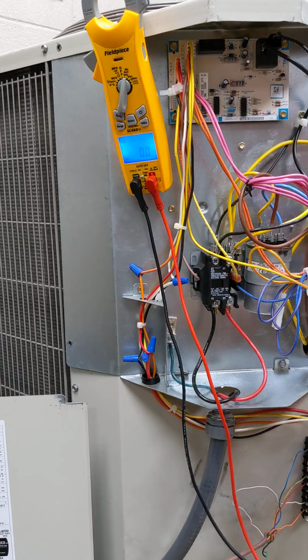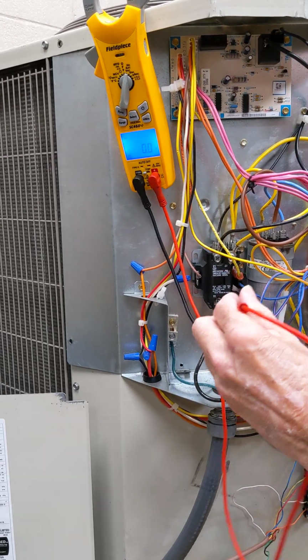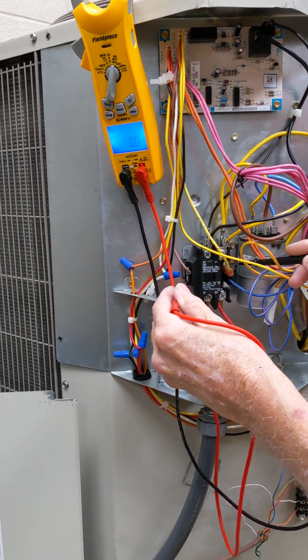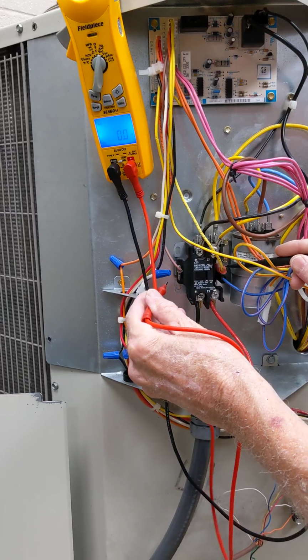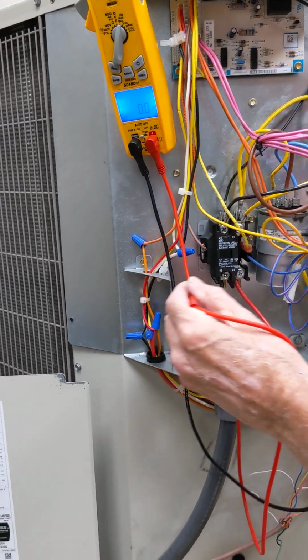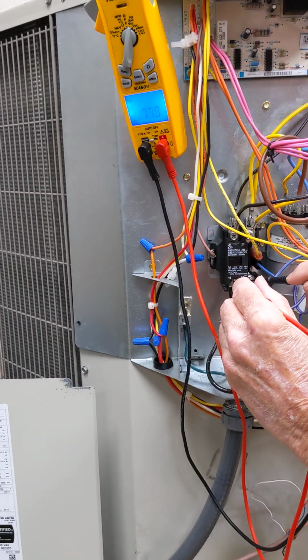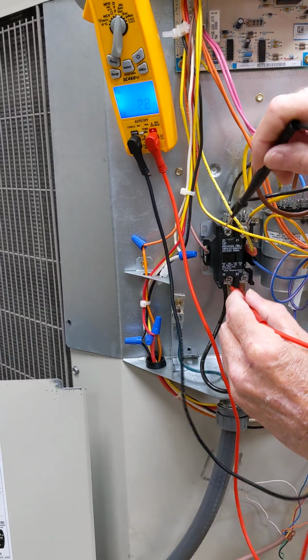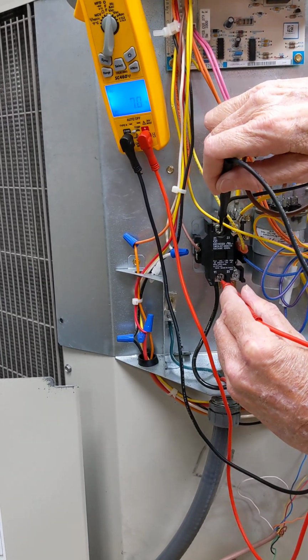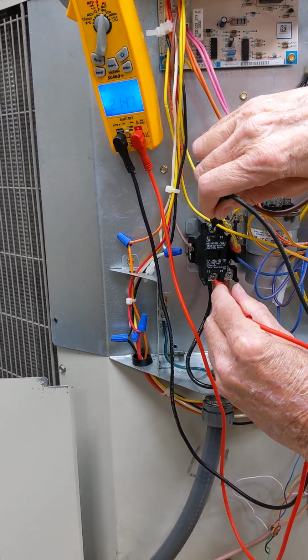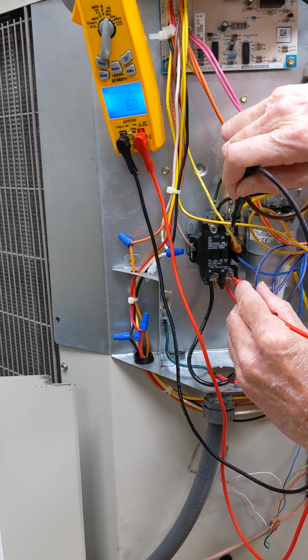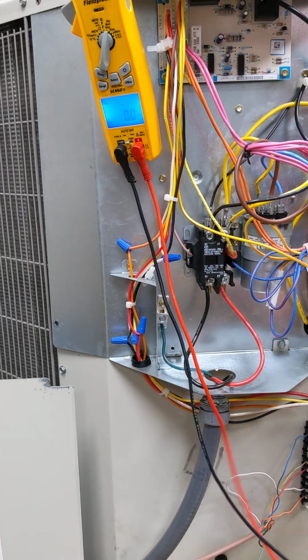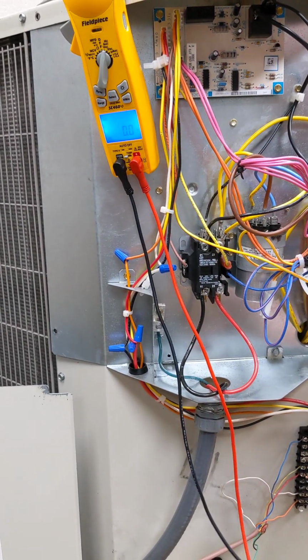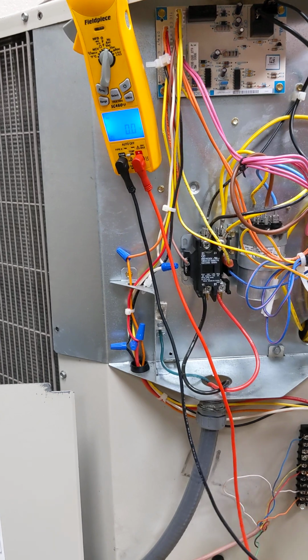So to summarize the contactor deal, I can check it hot with voltage, make sure the low voltage is getting what it needs, make sure the high voltage is getting what it needs, right? And I want to make sure that it's utilizing all the high voltage that it's getting for the motors. That's the hot check or the live check, okay?